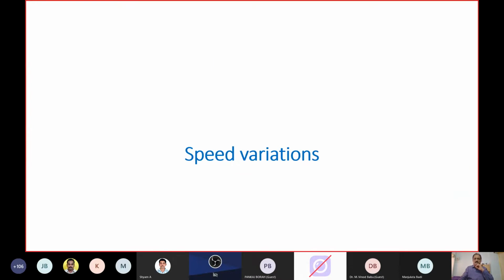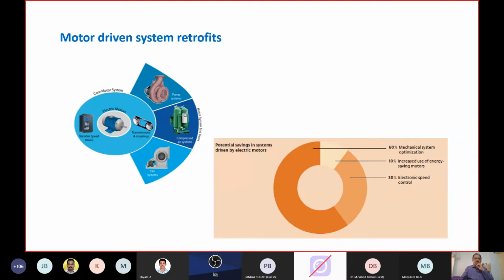So we go to the last choice available for improving energy efficiency, which is through speed variation. We saw in an earlier slide that almost two-thirds of the loads in industries are variable torque loads, or auxiliary power loads, or utility loads: pumps, compressors and fans. If you look at the opportunity available for energy conservation, 60% of the potential for energy saving will come from system optimization. Usually fans and pumps are oversized in industries for a situation which will never arise in the industry's life. So people typically oversize, and therefore they struggle to optimize the actual throughput with respect to the input. If you optimize through mechanical system optimization, you have approximately 60% energy saving potential. The electronic speed control, or in other words VFD, will offer you 30% energy saving. So 10% is the energy saving available through motors.